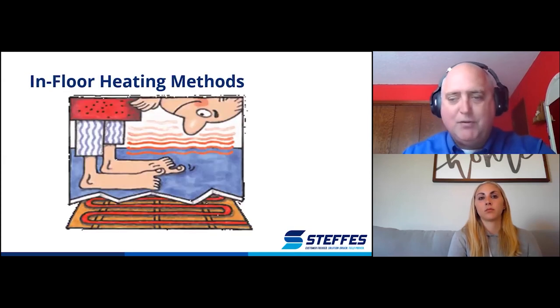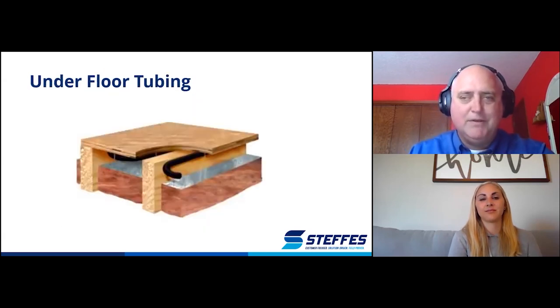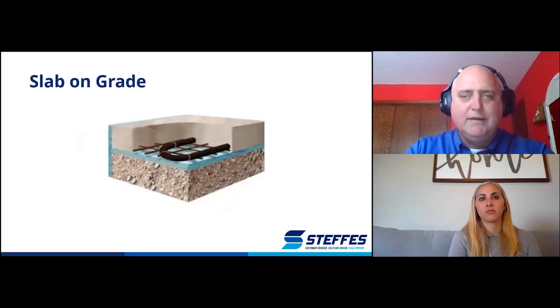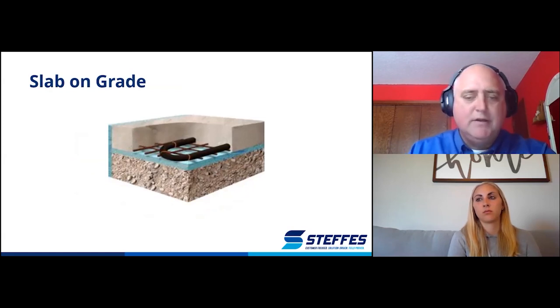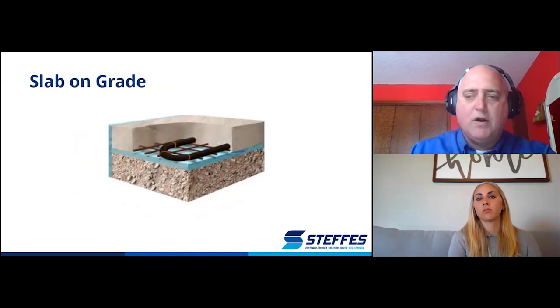And of course, people love in-floor heat and it always puts a big smile on their face. Some of the other applications, underfloor tubing, we can certainly do that. Slab on grade, basically any kind of hot water hydronic system, we can provide, like I said, up to 180 degrees, and we can lower that down. So if you were just doing in-floor and you only need 90 degree water, we can do that as well.